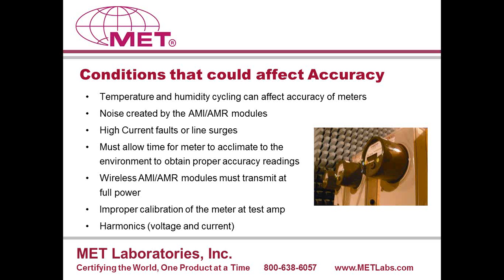There are operating temperature tests and relative humidity tests that'll go beyond that, where you want to make sure that the product can operate between plus 70 and minus 30 degrees C, and also operate at 85 degrees C at 95% relative humidity. So occasionally we do see meters that, at some of those peak temperatures, high or low, will simply stop working. So again, these external influences, the environmental aspects of the test, would affect the accuracy. Occasionally noise that's created by the wireless modules that may be installed in the product could potentially affect the accuracy. There are fault tests that are performed for current faults under test number 20, where you could also see problems there.